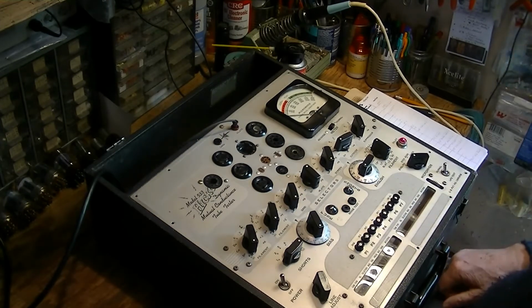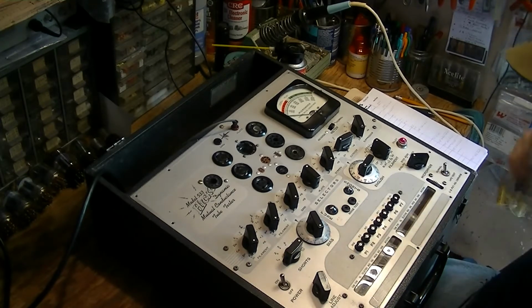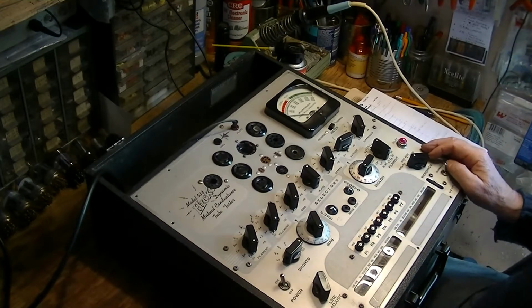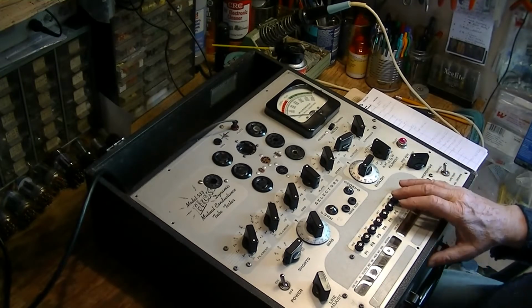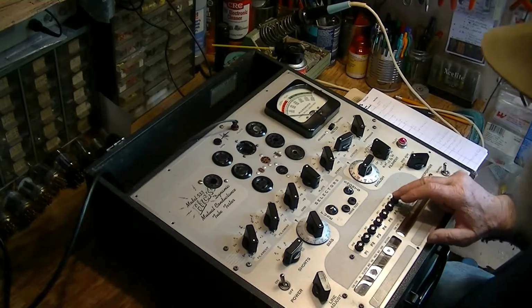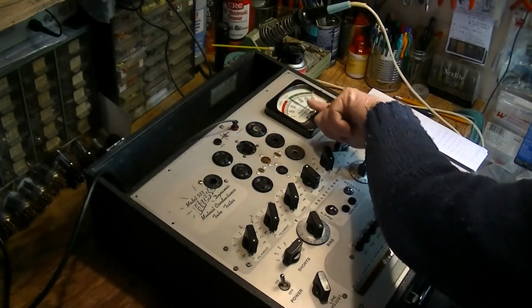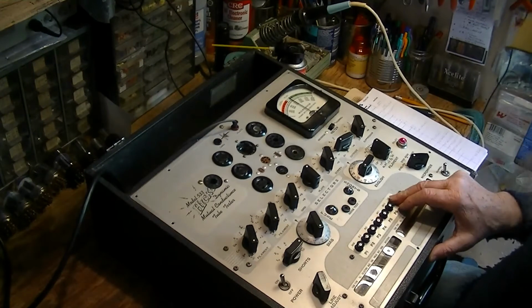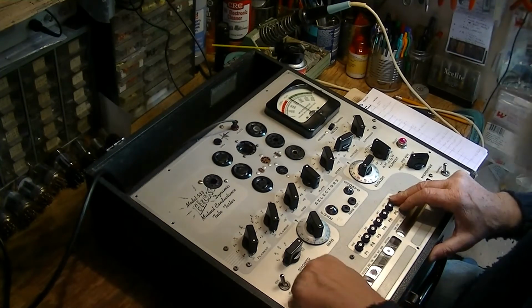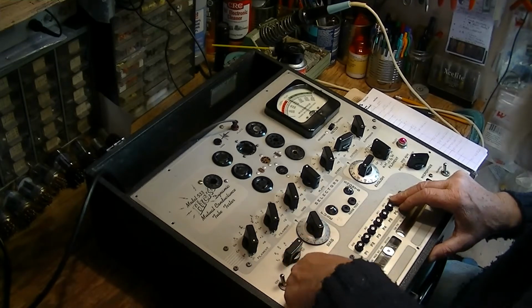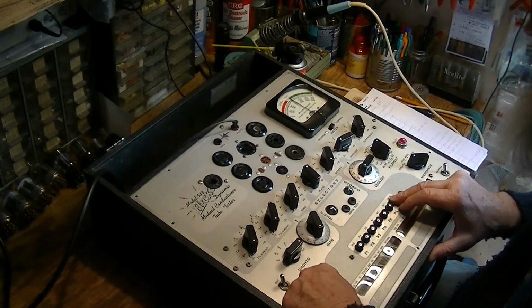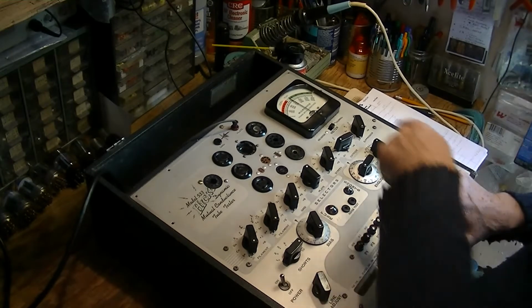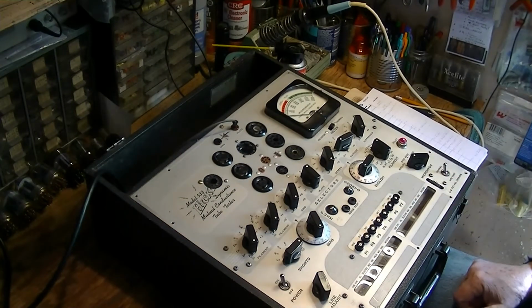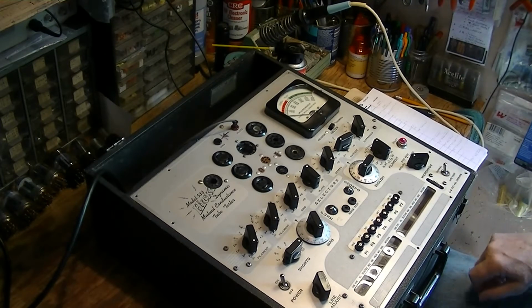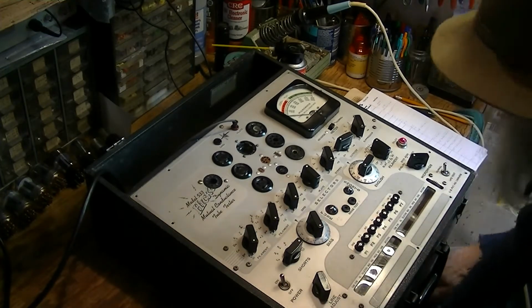First thing you want to do, now I've got a floor heater here, and I've turned it off. Because the first thing you do, after you let this thing warm up a little bit, is set your line voltage. On the far left here, P7 is the line adjust button. You push it, and the needle is supposed to line up with this little indicator line in the middle of the meter. Over here on the left-hand side, there's a line adjust pot, and as you turn that, you're compensating for changes in the line voltage. So to make sure that your calibration is correct, you just set this thing up at the beginning. And I've turned off my floor heater because every time that kicks in, the line voltage will drop a little bit and the needle will go a little bit and the calibration will change just a little bit. So that's the first thing.